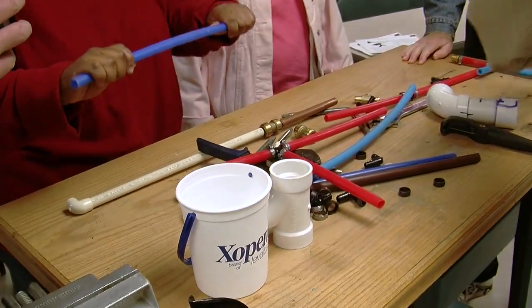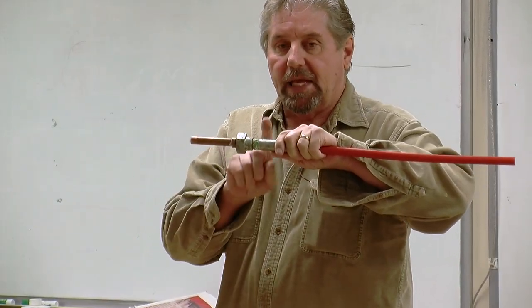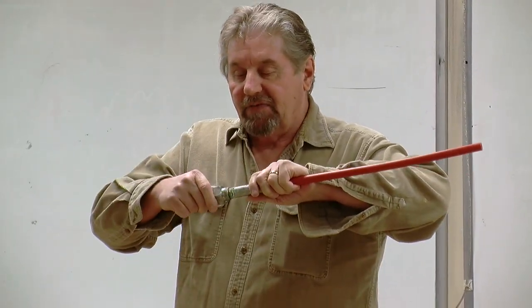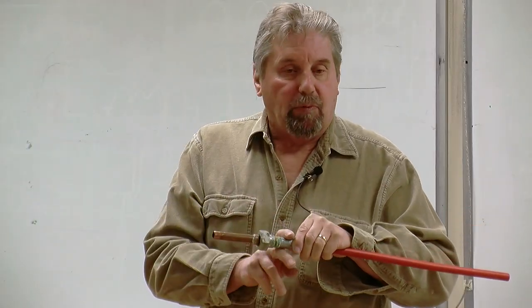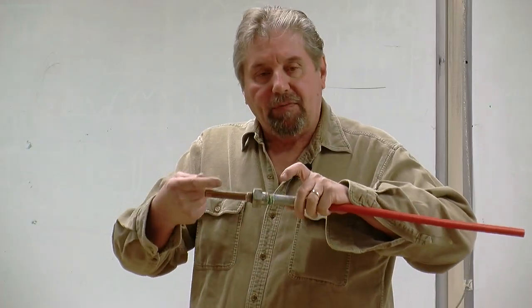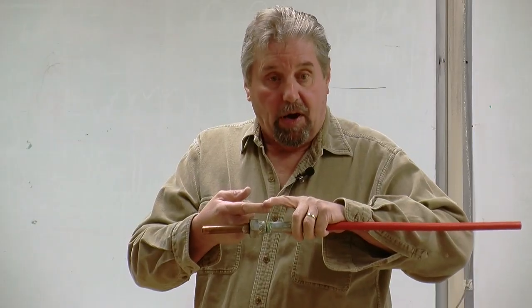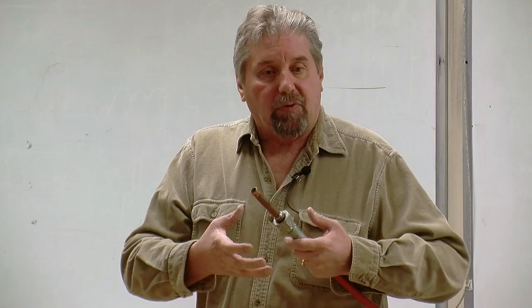We can talk about some of the different kinds of pipes. This is copper, this is galvanized, okay? This fitting that we have in between here is what they call a dielectric fitting, okay? Most likely you won't have to use this because your pipe will probably rust out before this electrolysis happens. But when you have two different metals that are touching each other, especially when you have water involved, they destroy each other. The metals work together and they corrode. So what you get is corrosion.